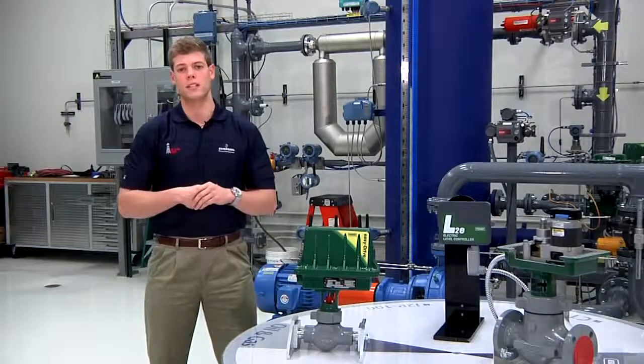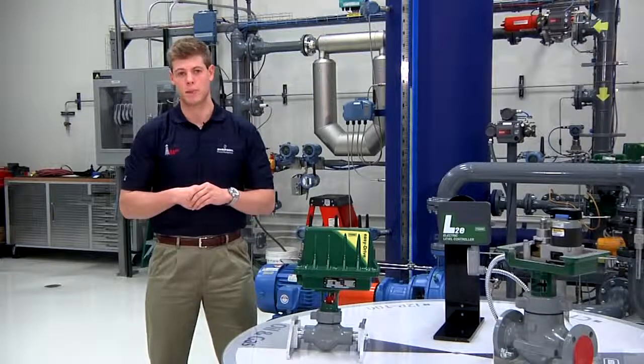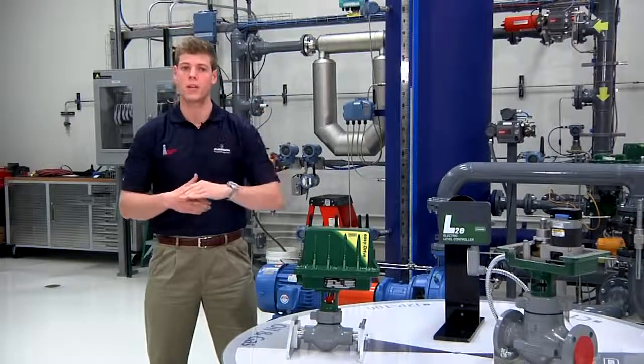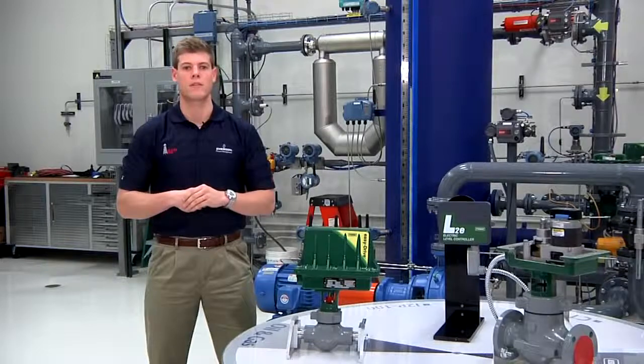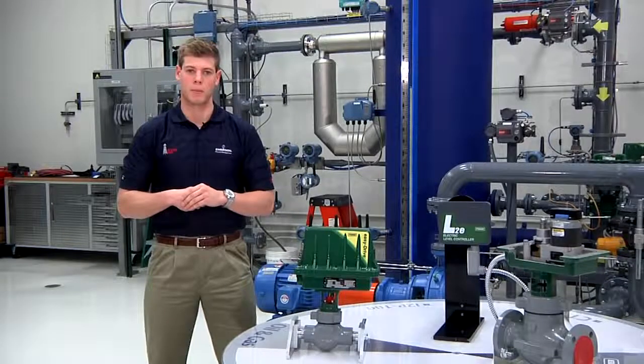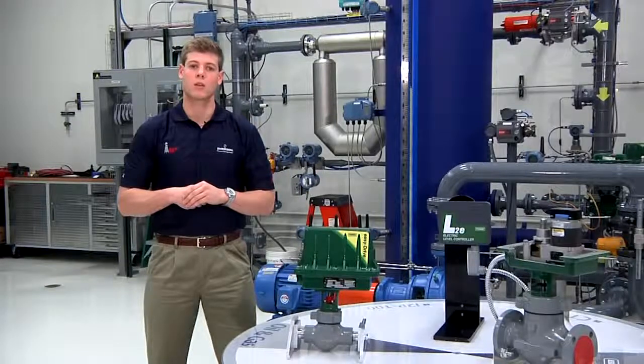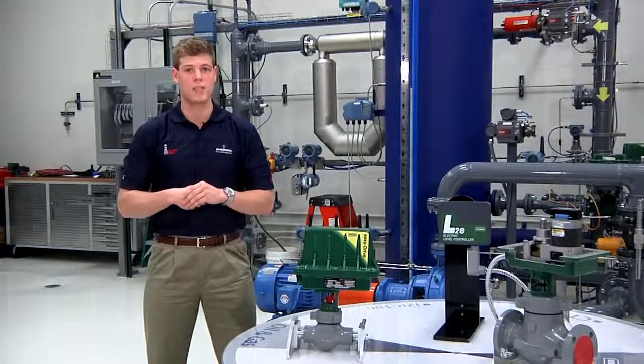Unlike other well-field designs, the Easy Drive electric actuator is highly responsive and can stroke from fully open to fully closed in under 6 seconds. Easy Drive is capable of reaching all rated shutoff capabilities for the Fisher field-proven D3 and D4 valve models. Using the D3 and D4 valve designs also provides an easily retrofittable option to replace your existing pneumatic equipment.